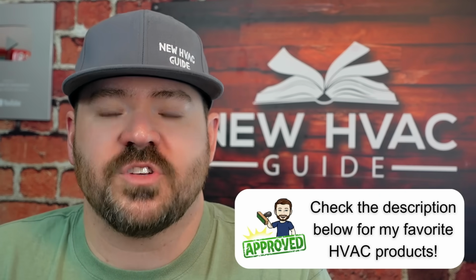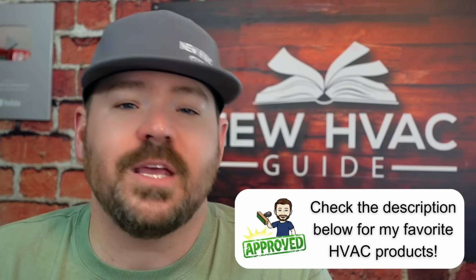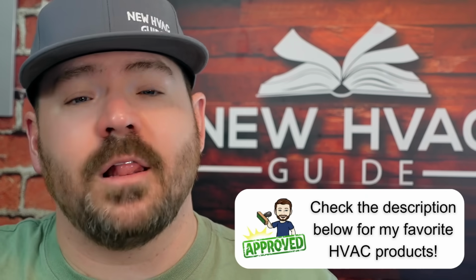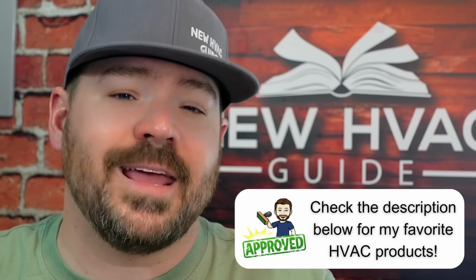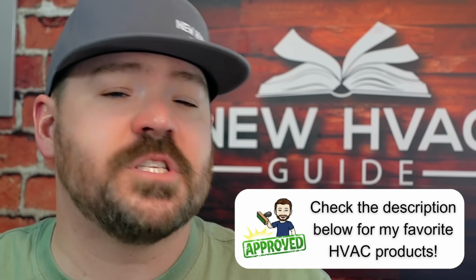It's kind of like the first point where we talked about POE oil. Back in the old days, if we had mineral oil or other types that didn't become acidic when it came in contact with moisture, guys would cut corners and it wasn't as big a deal. Today, airflow is dialed in, and a lot of times guys don't understand it has a lot to do with the efficiency of that system.